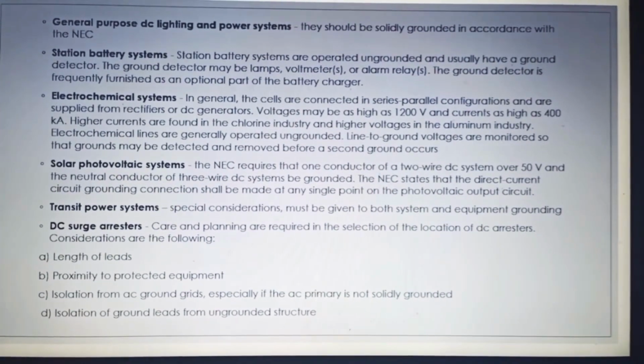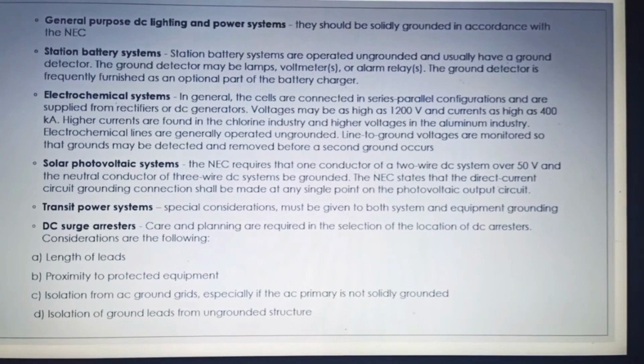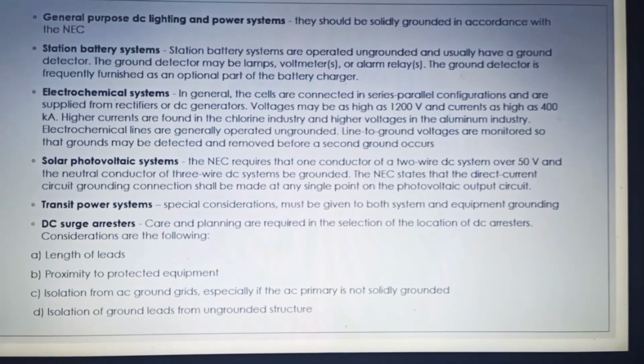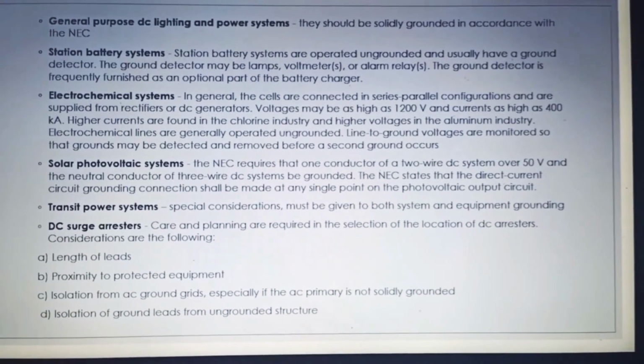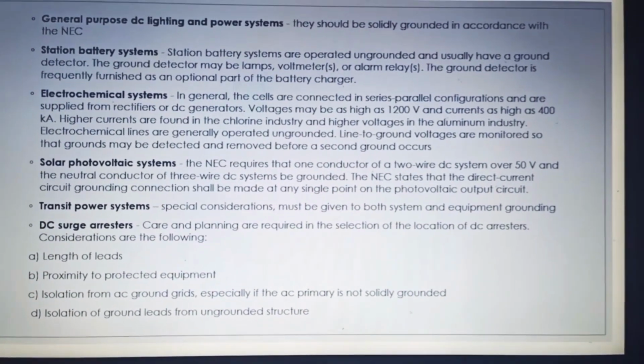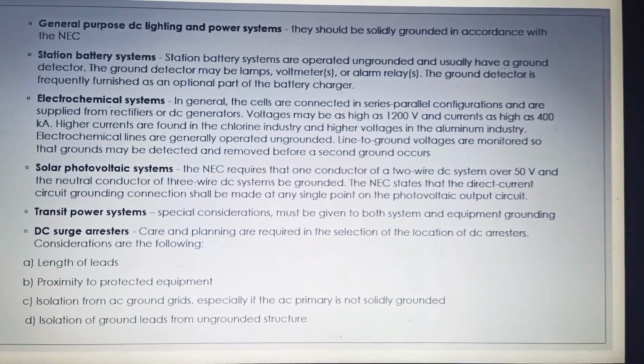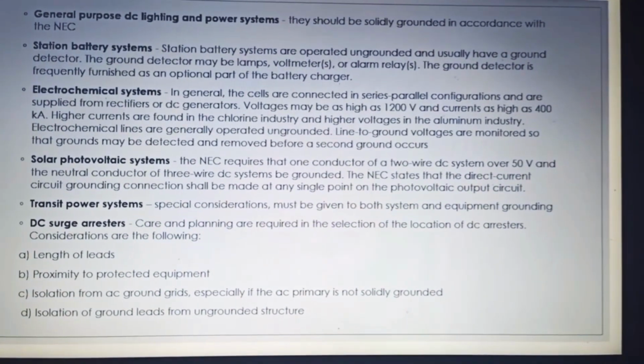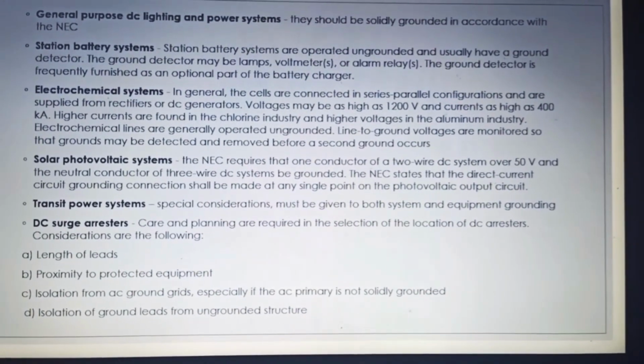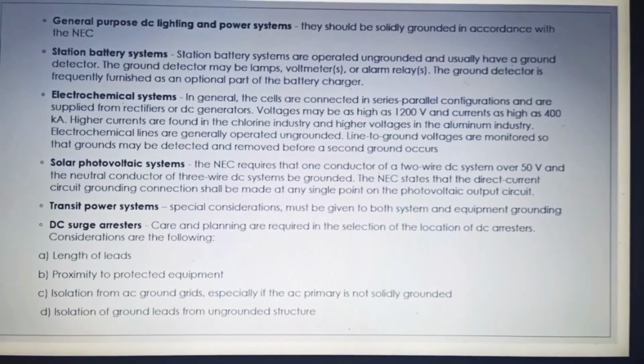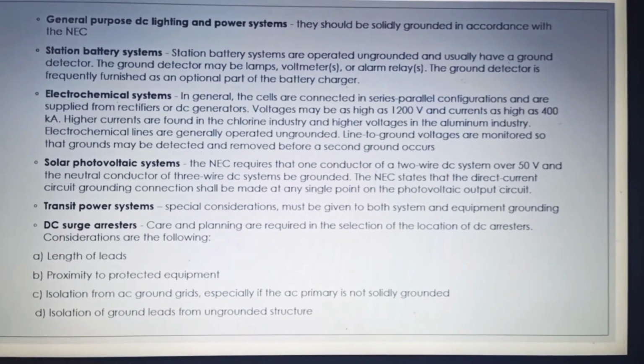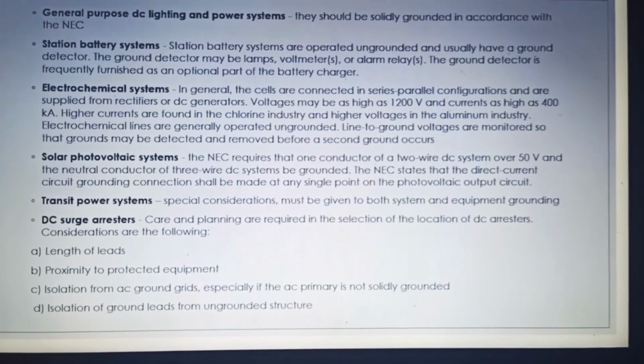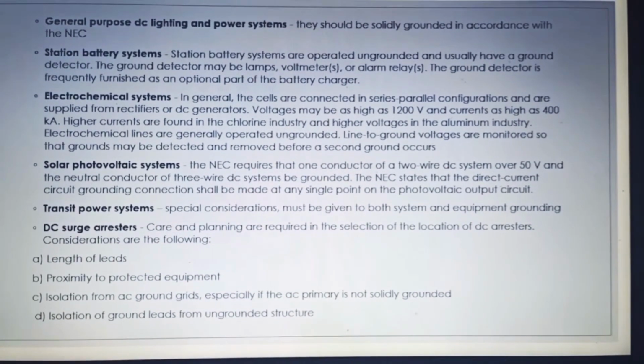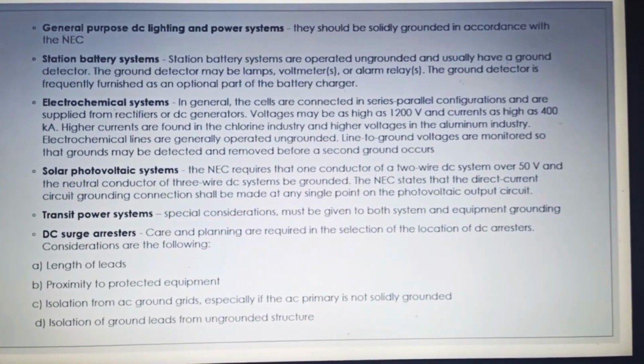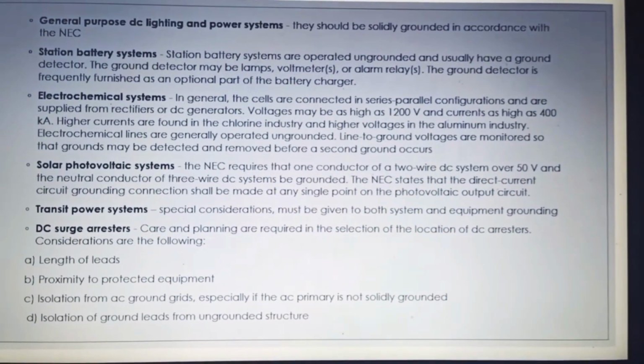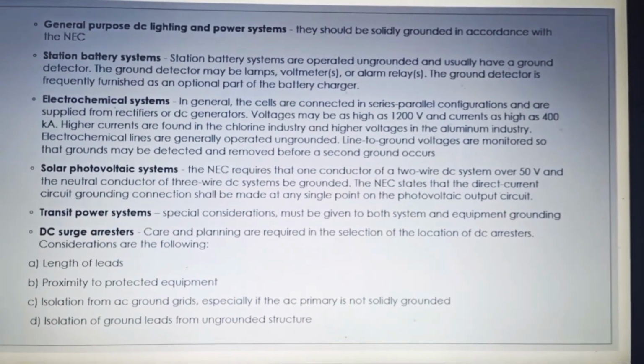The NEC states that the direct current circuit grounding connection shall be made at any single point on the photovoltaic output circuit. Surge arrestors are used in DC transit systems, and for the same reason, surge arrestors are used in AC systems: to clamp a voltage rise at a level the equipment can withstand and to dissipate the energy in the voltage peak. Care and planning are required in the selection of the location of DC arrestors. Considerations are the following: length of leads, proximity to protected equipment, isolation from the AC ground grid, especially if the AC primary is not solidly grounded, and isolation of ground leads from ungrounded structures.